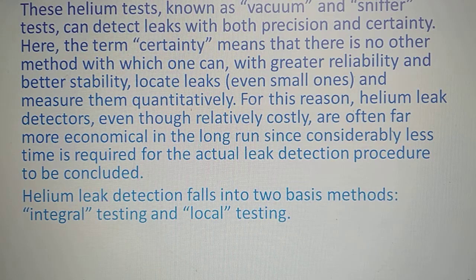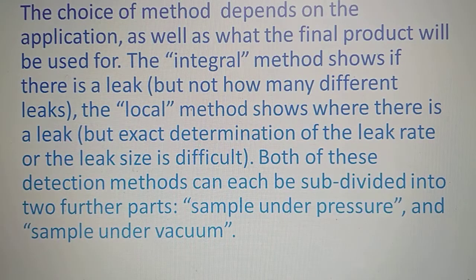Helium leak detection falls into two basic methods: the integral testing method and the local testing method. We need not study this in too much detail, but still we'll try to go somewhat deep into the integral and local testing. So let's go ahead. We're going to study both cases, and the choice of method that you use for leak detection depends upon the application as well as what the final product will be used for.